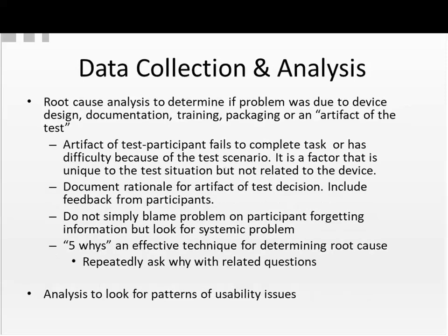Now let's talk a bit about root cause analysis. You want to find out if the problem is due to the device design, to the documentation, to the training, to the packaging, or if there's a, quote, artifact of the test.